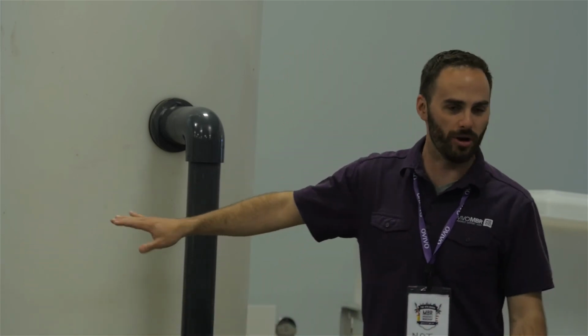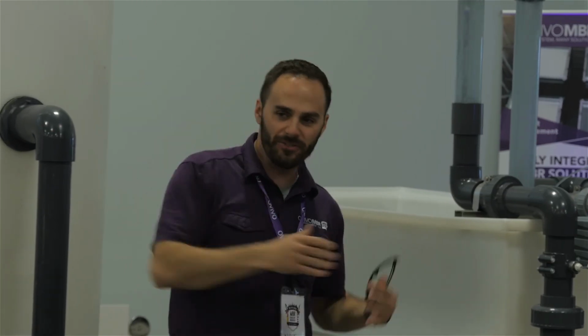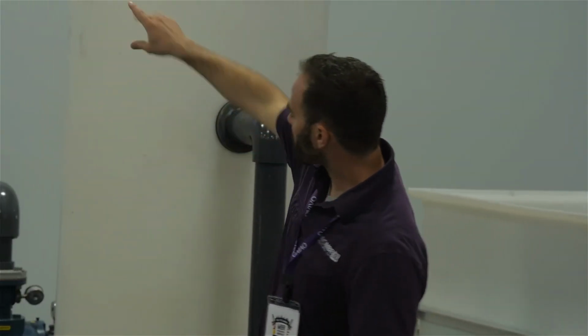A tiny little hole that big means that when you come in the morning and your plant's been in intermittent mode, you have to reprime that piping. We have a pretty simple prime situation here. We have a positive displacement pump, but that's not true in most of our plants. So if you have this issue, you might have a fight when you show up trying to reprime your piping, especially if you have to bring that liquid up 15 feet or something like that. Then you're going to have a hard time.